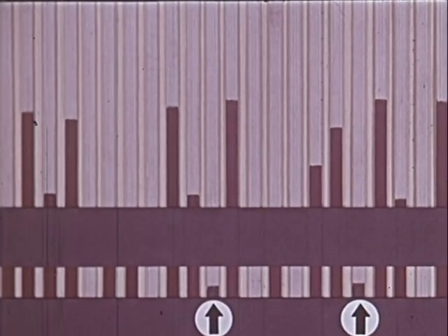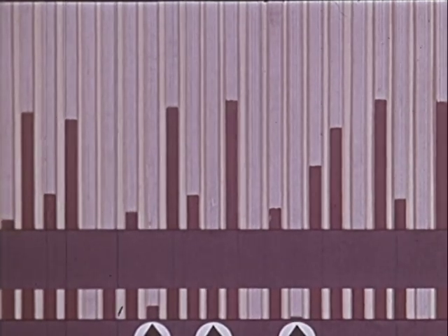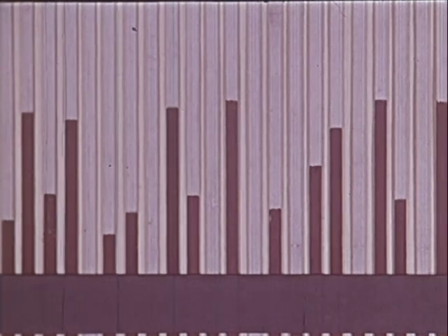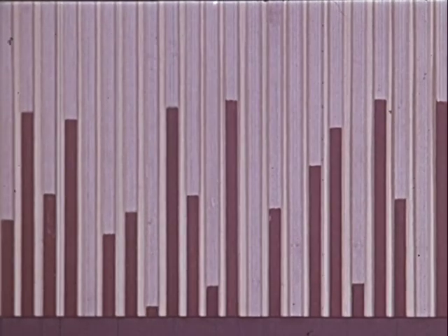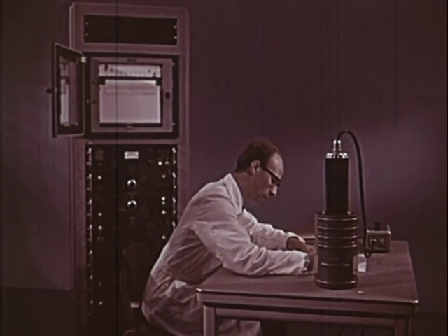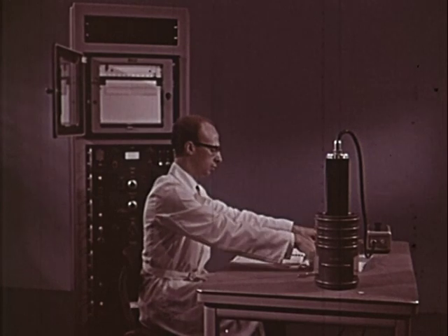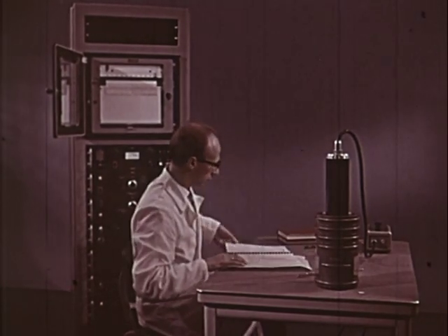To scan a spectrum, pulses are counted successively, each time tuning in, so to speak, on a certain pulse height. The numbers of pulses are plotted on a graph corresponding with the position of the channel. This is the sliding channel method of operation. The channel width remains constant during the scanning period. That means that relatively, the channel width continuously increases with decreasing channel height. The procedure has certain drawbacks when scanning spectra with a great energy span or in analyzing complex isotope mixtures.